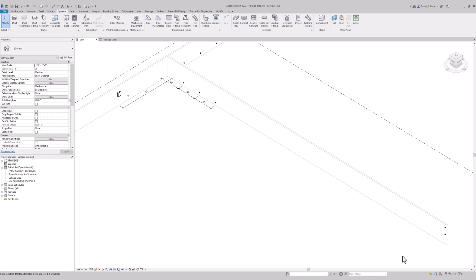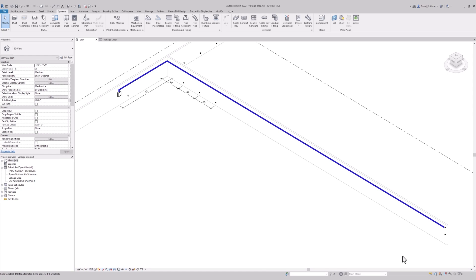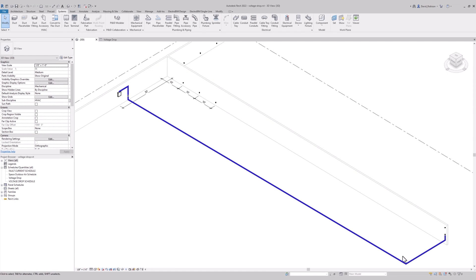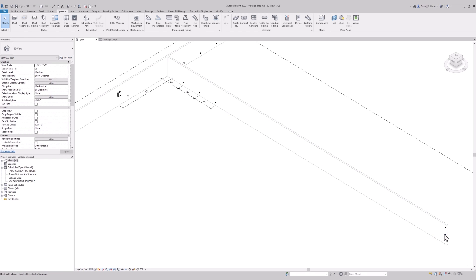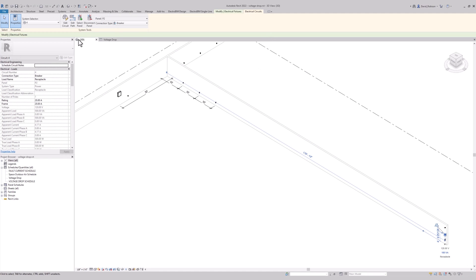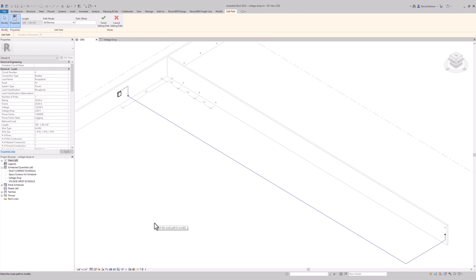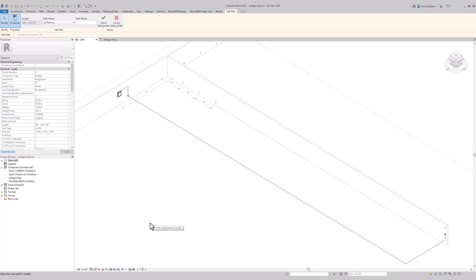I actually have two circuits set up. The first has just one receptacle in that top right corner. The second has two receptacles — one right next to the panel and one farther away. In the first circuit, all of the load is going to be in that one receptacle, so the voltage drop is what Revit is going to calculate. For the second circuit, we have the receptacle closer to the panel with most of the load there, and then another receptacle farther away. If we take a look at the path in Revit, it's tracing from one receptacle to the other back to the panel — it takes into account location, but puts the whole load of the circuit on the farther receptacle.